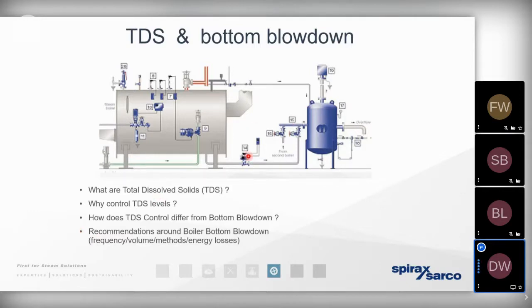And the bottom blowdown valve, well, if we open that valve for a couple of seconds, once a shift, every 8 hours, then the pressure that the steam boiler is working at will blast that sediment away across the valve to a much lower pressure. And then we just close the valve, and the falling water level is recognized by the level control probes, and that calls for that water to be replaced by a lower concentration of water that comes from the feed tank. The point is, we need to recognize exactly how much blowdown we need to be performing. Because if we perform too little blowdown, we're not getting rid of all of the sediment. If we perform too much blowdown, then it's a significant waste of energy. That hot water that's going to waste needs to be replaced.